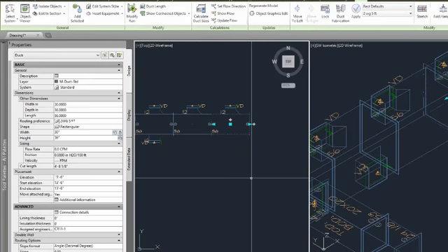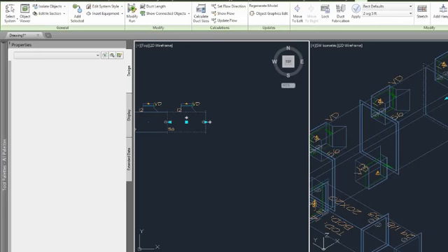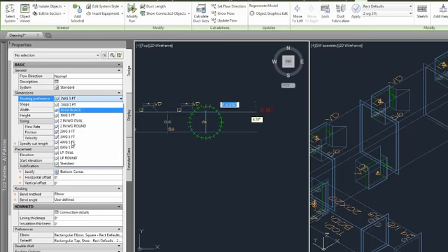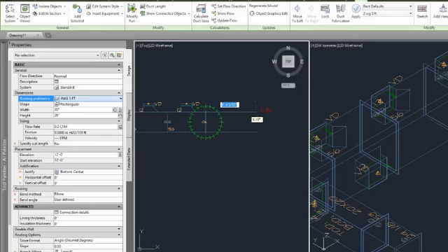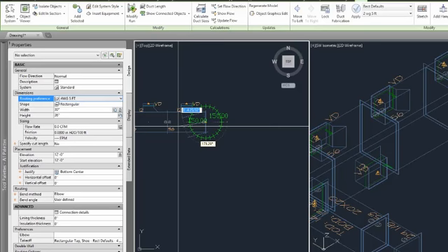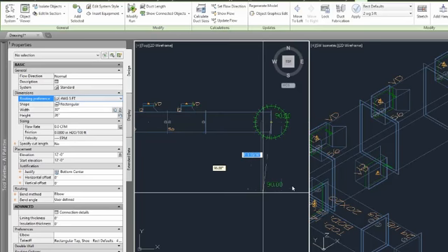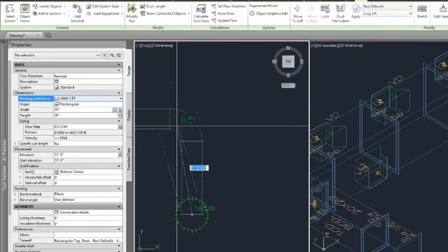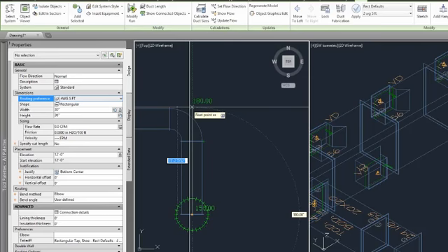Another tool that EastCoast has added when routing ductwork is that you set your routing preference as you're drawing. So maybe now I want to choose a different routing preference. I want to go to a 4-inch water gauge. And I go to put in my elbow, and it's asking me what elbow I want to use. That's because my 4-inch routing preference probably doesn't have an elbow set up. So let's just go in there real quick and look at it.